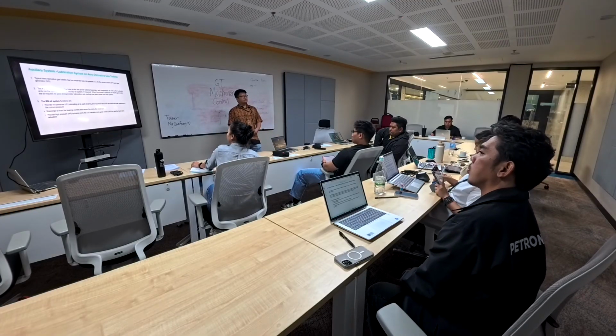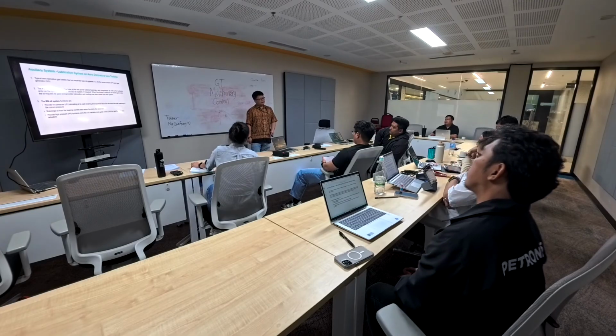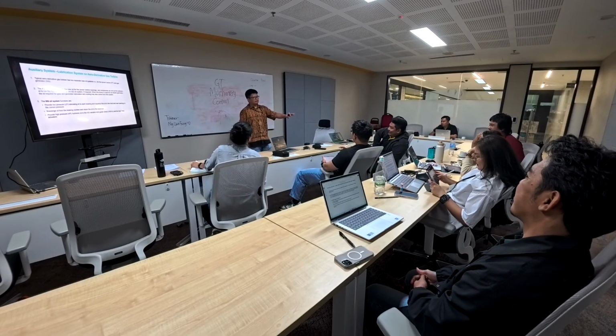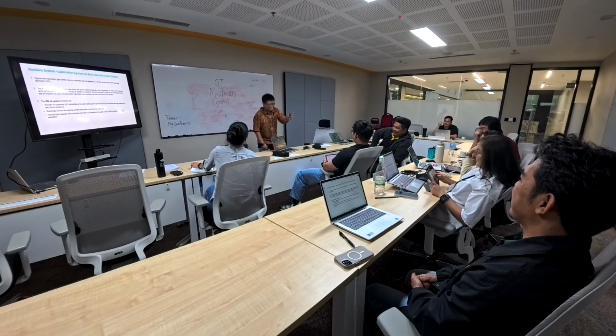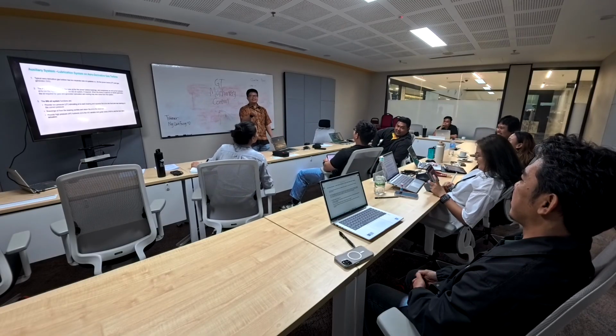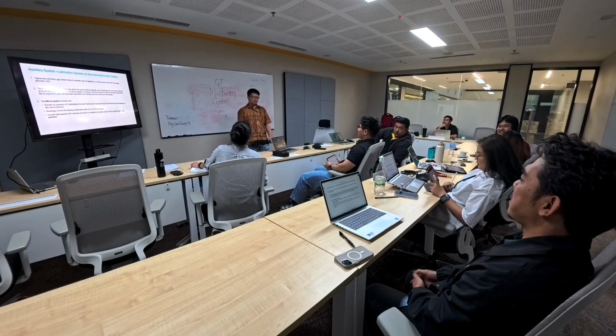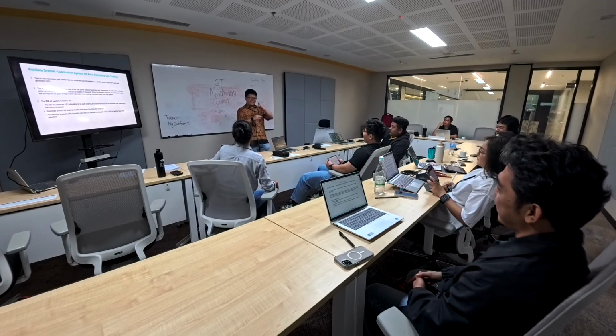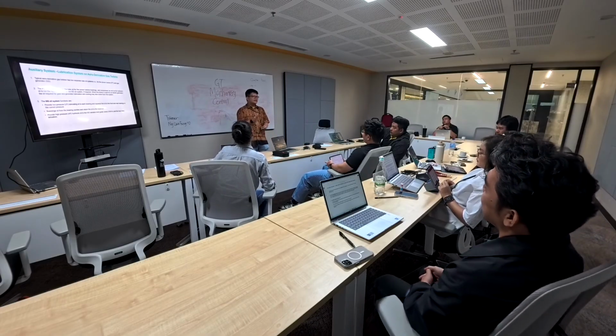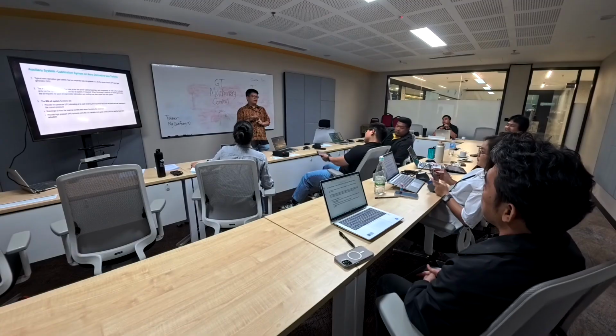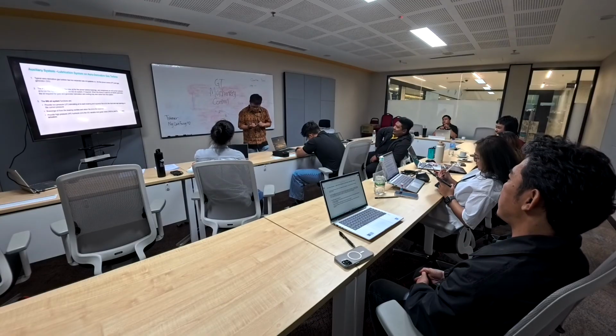So if you come across RB211, your GG lube oil pump, normally how many stages does it have? I'm not expecting Indra to answer. Tony? Sukri, do you know? You have opened it before, right? So normally it has 5 stages. It's a stack, a vertical pump. So it has 5 stages: one is for LP, one is for HP, and another 3 are for scavenging.